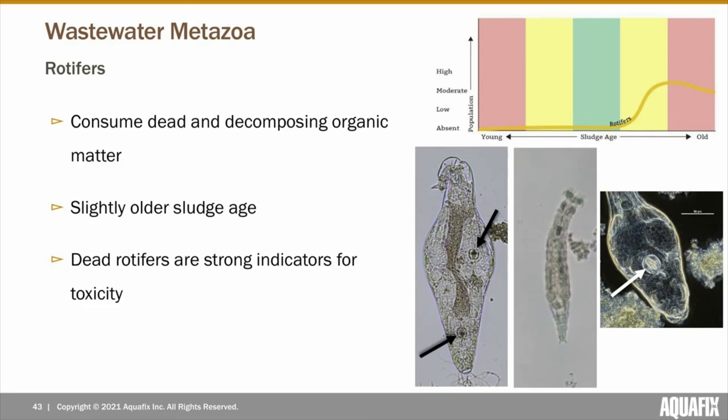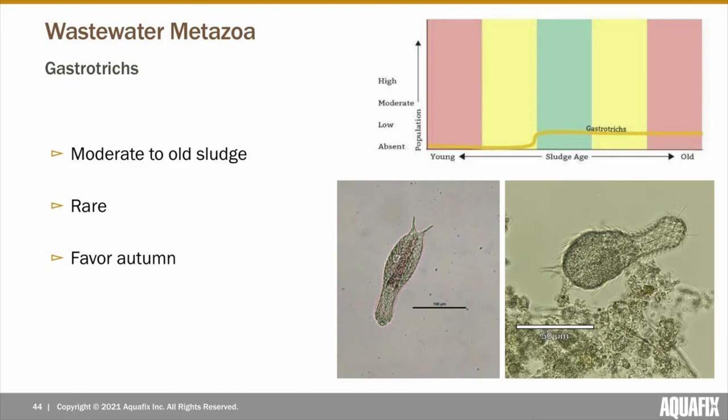If live rotifers are observed in your plant, they're indicative of a slightly older sludge age. However, if dead rotifers are present, they're indicators of toxic conditions, as they are usually the first to be affected. Gastrotrichs are also indicative of a moderate to older sludge age. They're not common, so not a lot is known about them, but we tend to see them a little more frequently in the autumn, though we're not exactly sure why.